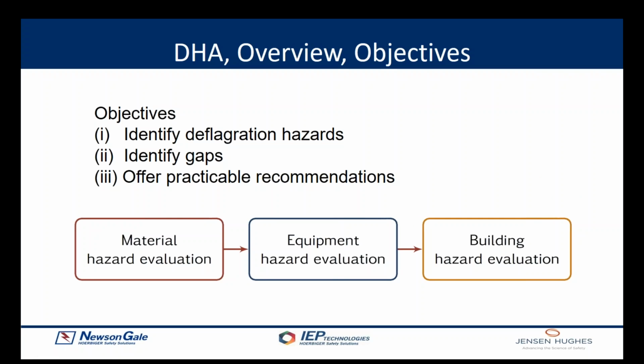So what is a DHA? Basically, the objectives are straightforward. There's three. You want to identify credible deflagration hazards, credible explosion hazards, credible fire hazards. The next objective is to identify, if it's an existing facility, what, if any, are the gaps between what is considered good engineering practice, exemplified by the NFPA standards, and existing conditions. If it's a proposed facility, you want to identify gaps between the proposed basis for safety, the proposed safeguards that you're endeavoring to provide for your plant, and good engineering practice. The third objective is to offer practicable recommendations to address those gaps.